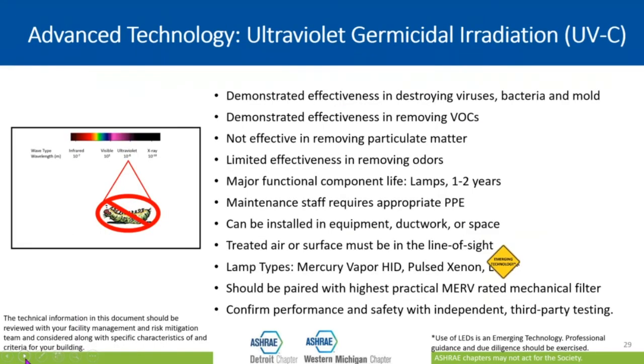In addition to the mechanical filters, we see folks adding some sort of advanced technology like UVGI, ultraviolet germicidal irradiation. We're using energy in the ultraviolet range that renders the virus and other microorganisms inactive, right? So when you want to go beyond the typical mechanical filter, then you can include some of these technologies. They can be installed in ductwork or in the air handlers, or they can be installed as standalone equipment.